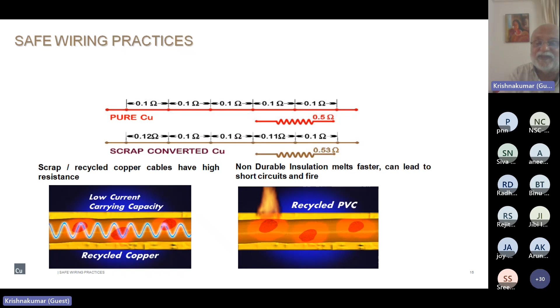The same is true with PVC, which also gets recycled. So if it is not virgin ETP copper or virgin PVC, it will all land up in problems. There can be hot spots in the conductor and weak spots in the PVC, and if by chance they coincide, the havoc is certain. This can be eliminated by resorting to top brands who care for their name and ensure that the wires coming out of their factories are foolproof and conform to standards.